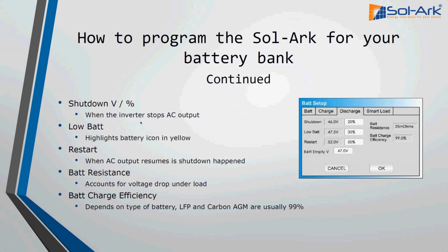Battery resistance is just going to be the resistance of your battery bank. We have some example values of these in our manual. You can also measure it, or you can get it from your manufacturer. But 25 milliohms is pretty good for most cases, so usually, when in doubt, you can just leave it as the default. We use this for calculating the allowable voltage drop under a load. So if you have thresholds set for a particular voltage for time of use settings or something, it will adjust that value based off of how many amps are coming in or out of the battery, just so that everything is more accurate.